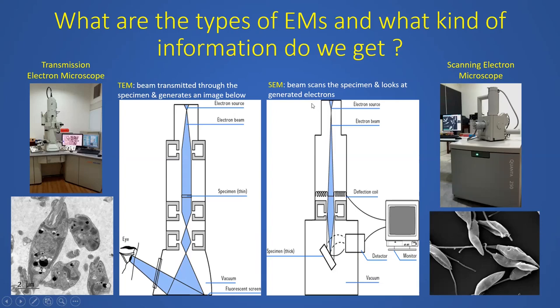So for a SEM, the beam scans the specimen and looks only at generated electrons. The electrons are then processed, and the image can be seen on the screen. It cannot be seen using the eye. Another major difference is that a scanning electron microscope does not have an objective lens, which is typically the heart of the microscope. For any microscope, the objective lens is the heart of the microscope. So here for a SEM, as we'll see later on, there is no objective lens as such.